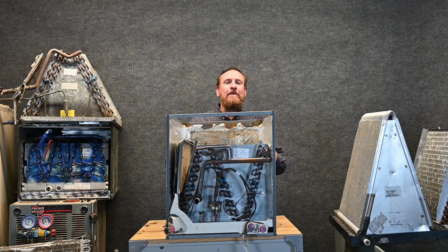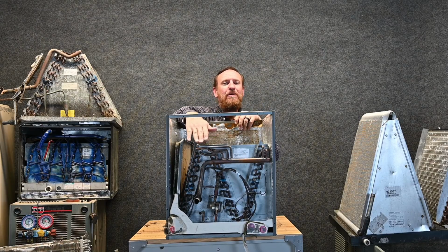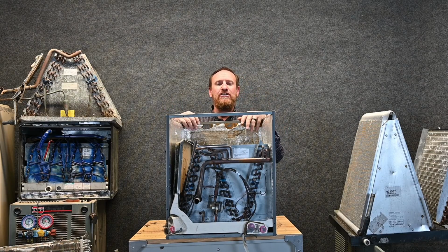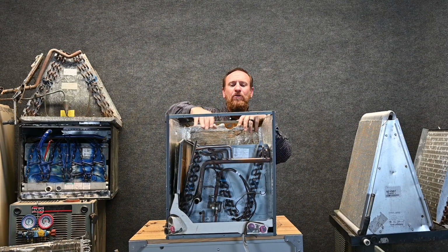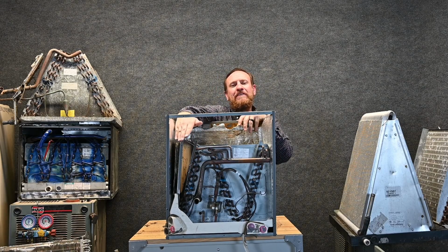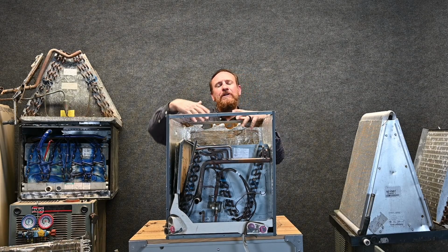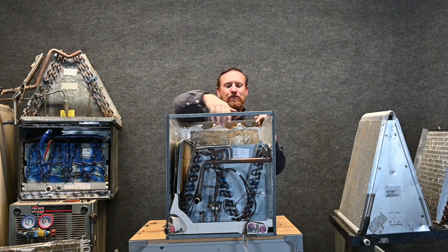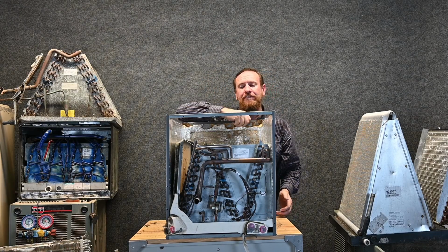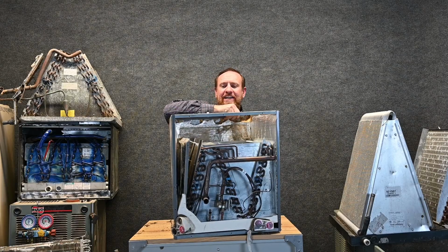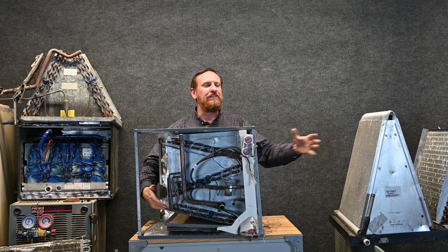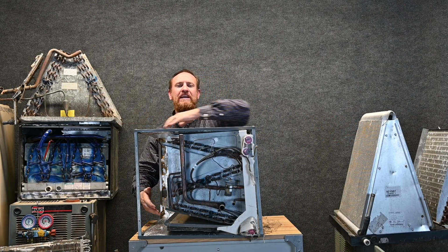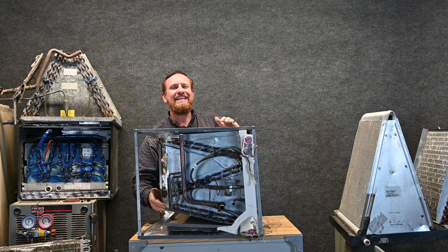So if you don't need the box, you just slide this out of the new box, slide it into the old box, and you just chunk this or throw it away. But this is a cased coil and this is an A coil. But notice we have this other drain pan on the side. This is what we call a multi-position coil. I have a drain pan at the very, very bottom for when it's upflow, but also if we turn it to the side, we'll be able to catch the condensate as well. So if my airflow is going this direction, I'll be able to still collect that condensate in this drain pan right here.